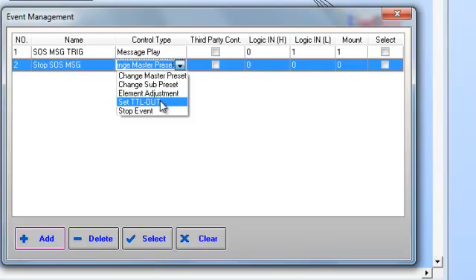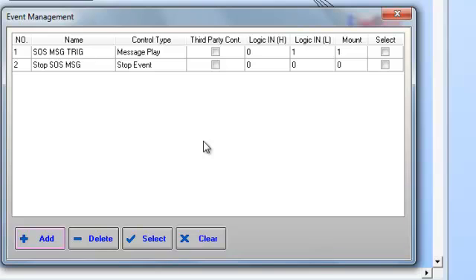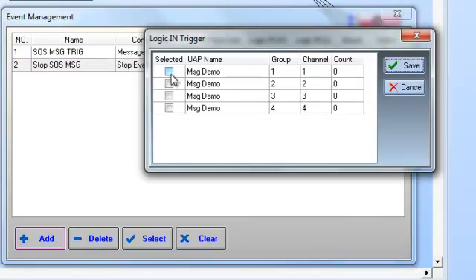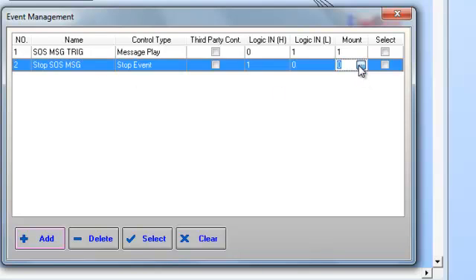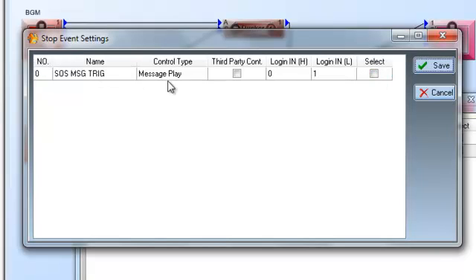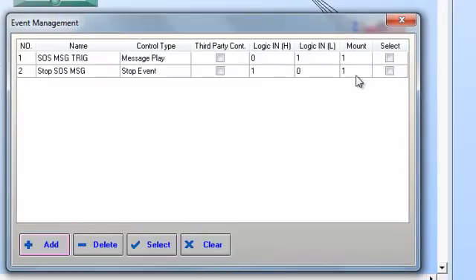With a control output device I can simultaneously do things like unlock doors, turn off strobes, turn on strobes, lights, or beacons. One of the control type options is called a stop event, which is designed to stop anything continuous or repeating. Now I have logic-in-high and logic-in-low. I want logic-in-high to be channel 1. So when channel 1 goes low we play the message forever, and when it goes back high — contact released — I want to stop the event. I select the SOS message play event as the one to stop, save it, and we're ready to go.